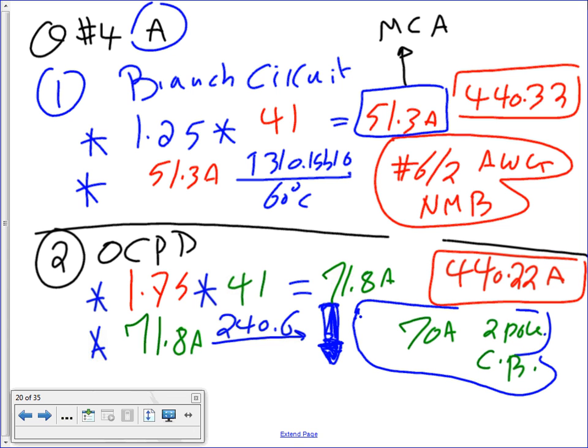Now, having said that, please write yourself a note here. This will be called maximum overcurrent protection, MOP. On the nameplate, this will be listed as maximum overcurrent protection. It's on the test on Friday. It will ask what MOP is. MOP is the maximum overcurrent protection device. That's the size of the fuse or the circuit breaker that you can use. So in real life, these two numbers will be given to you on the nameplate. All you have to do is size them, stick them in there. Okay.